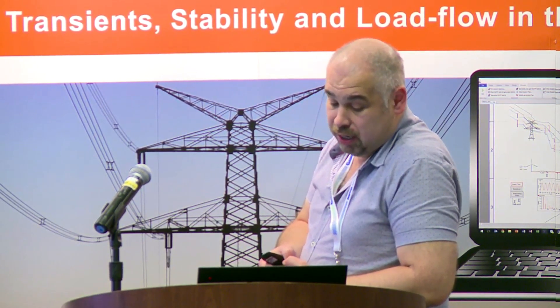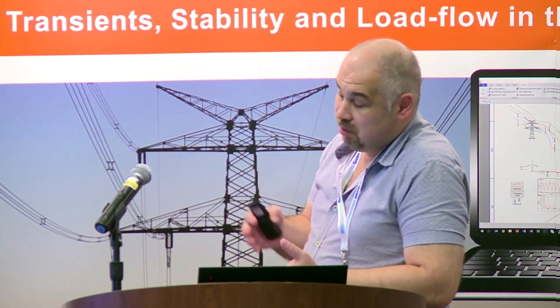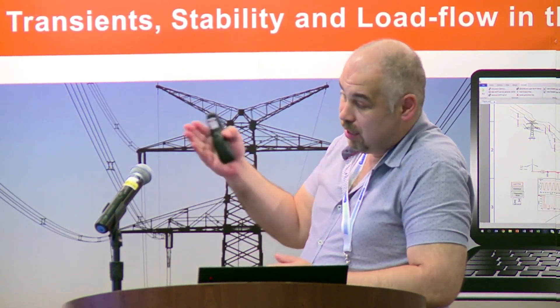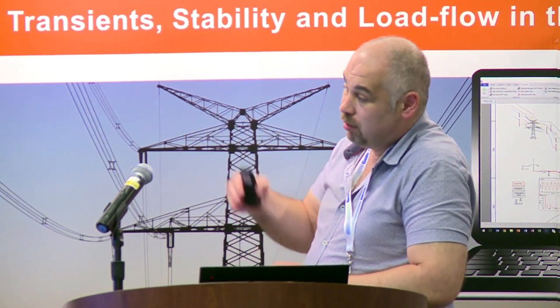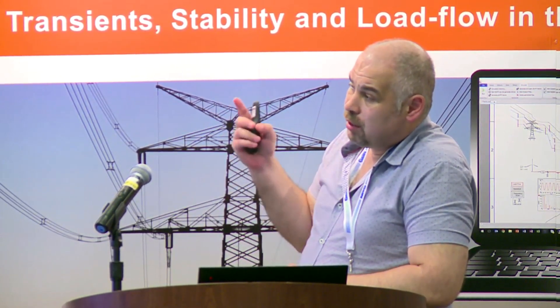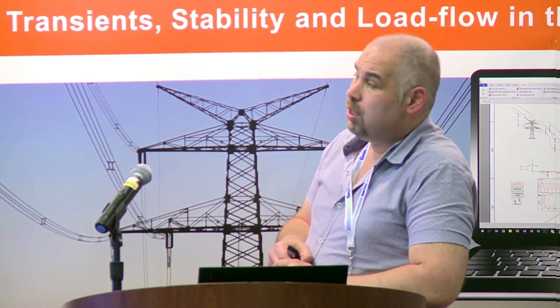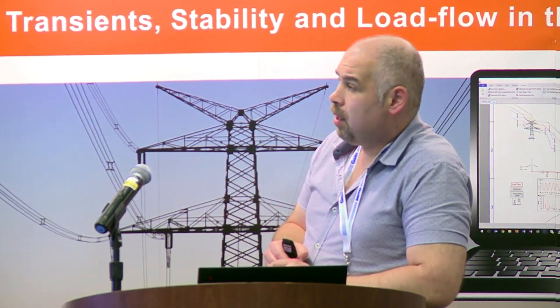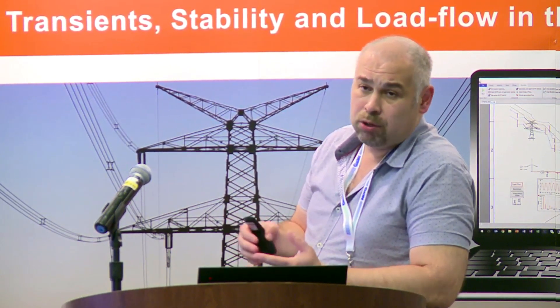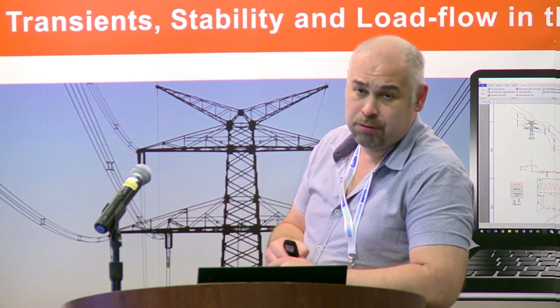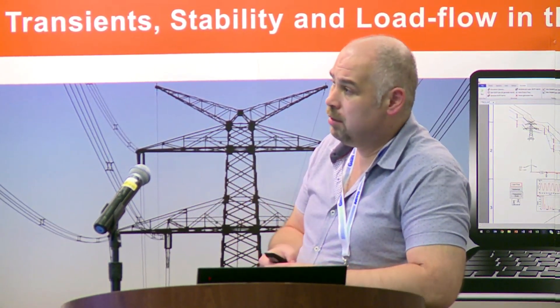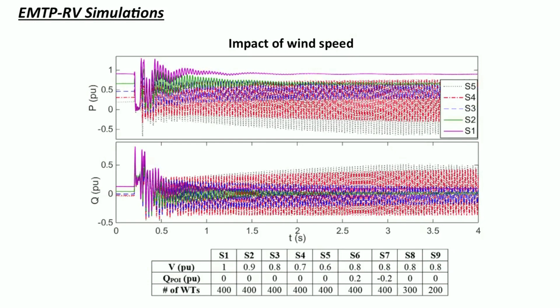We are not able to check the impact of measuring filters and PLL dynamics on SSCI with the eigenvalue approach. One important thing: this approach requires the complete model of the system, so with manufacturer black-box models you cannot use this approach or design anything. We then perform EMTP-type simulations, and the results are correlated with the eigenvalue analysis, though there is quite a significant difference in the damping of the SSCI mode.